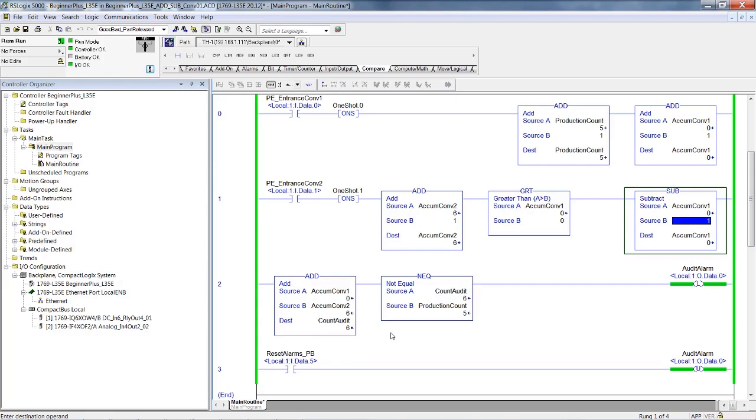How could an object leave conveyor 1, pass through the photo eye onto conveyor 2 if conveyor 1 is empty? It cannot. Therefore, if the photo eye on conveyor 2 is blocked, incrementing conveyor 2 count and attempting to decrement the count on an empty conveyor 1, that is a problem.